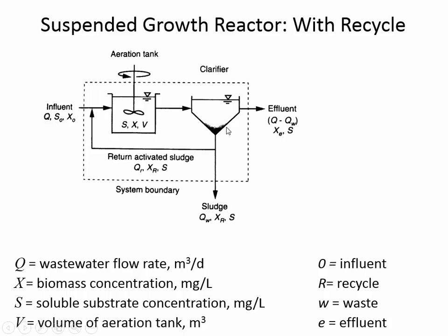But when they're sitting down here in the clarifier, not only are they not getting food, but they're not getting oxygen either. There's no aeration in the clarifier. If we aerated the clarifier, then the solids wouldn't be able to settle. So you notice there's no mixing that happens in the clarifier. So by the time they finally get over to re-injected into the aeration tank, they're activated. The sludge is activated. And what that means is the sludge is ready to start eating. So that's the purpose of the recycle.